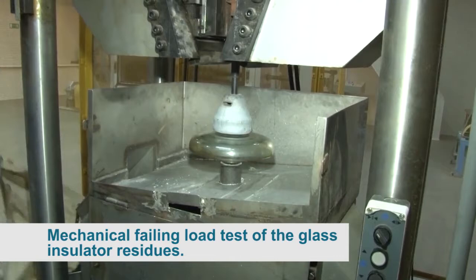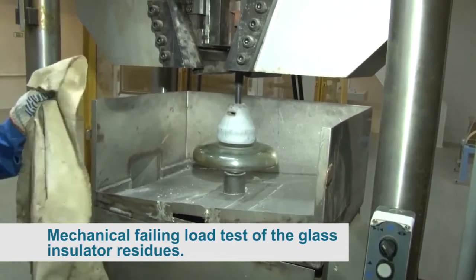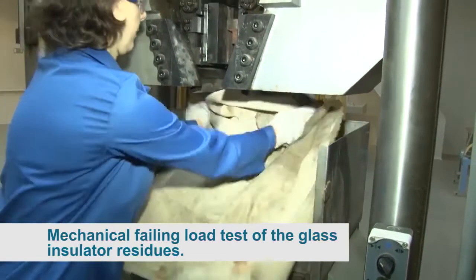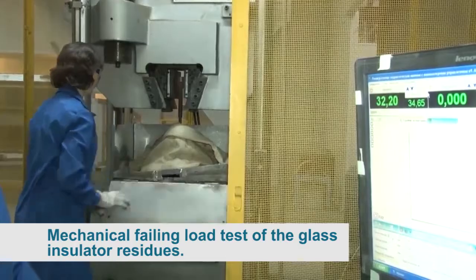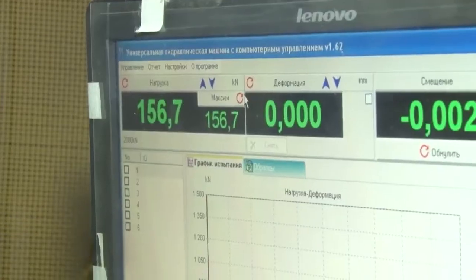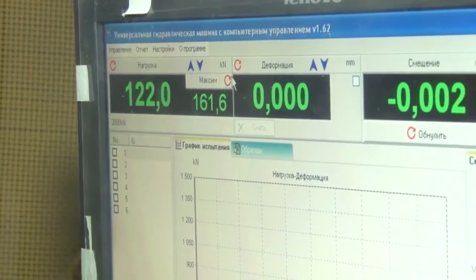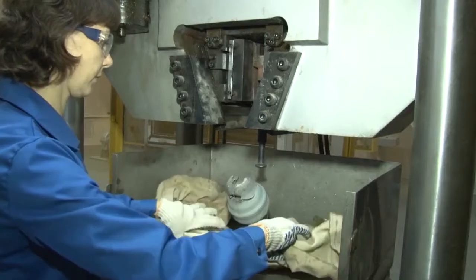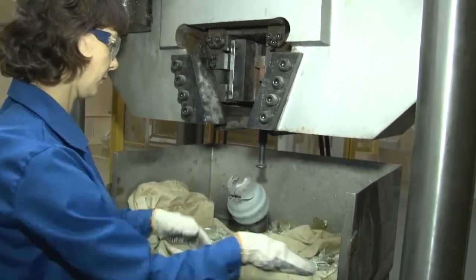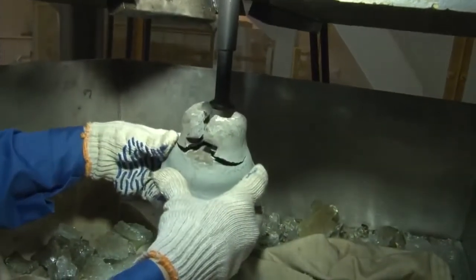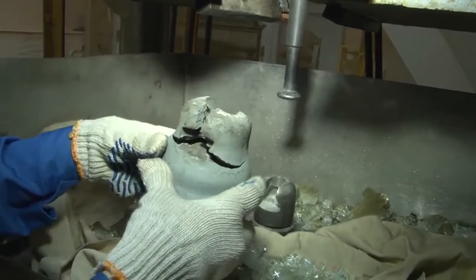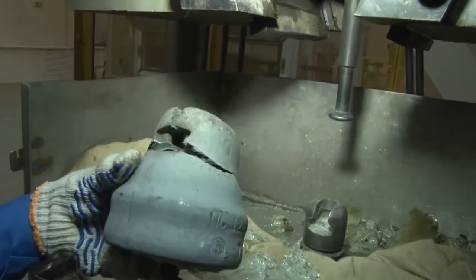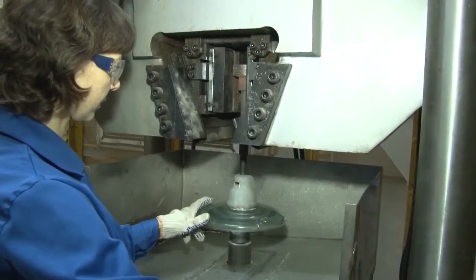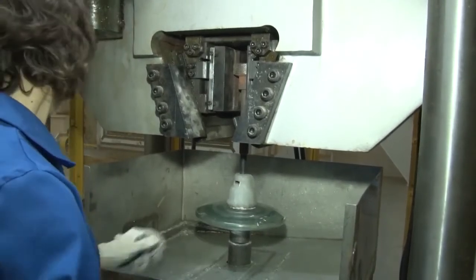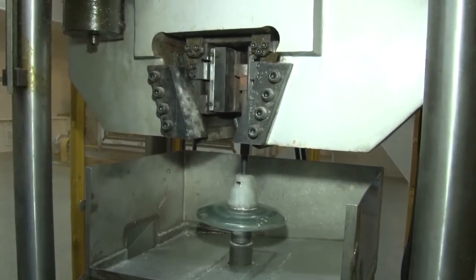Mechanical failing load test of the glass insulator residues of type PS12A and PS70E. Achieving tension loads of 24 kilonewtons and 14 kilonewtons respectively, the glass insulating part was shattered by the mechanical shock in the test machine. The remaining part is the residue. Then the load was increased until the residue was crushed. Insulators passed the test because the residue was crushed at a load higher than the standard. Insulators meet the IEC requirements.